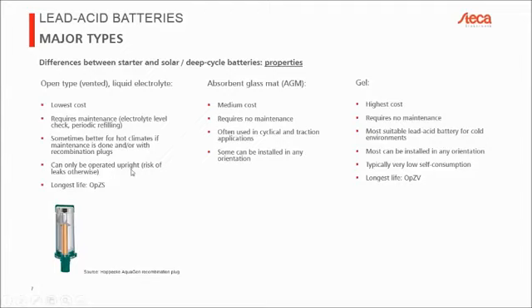Typically, these batteries can only be operated upright because, again, it's a liquid electrolyte, so if you leave them on their side they will leak. Of these batteries, the one with the longest life is the OPZS, which is simply a type with tubular electrodes.